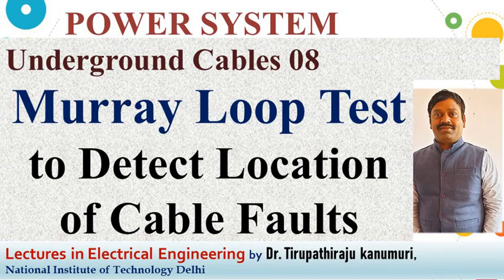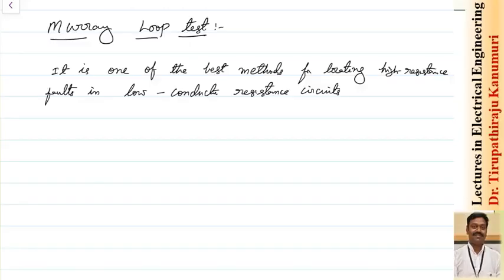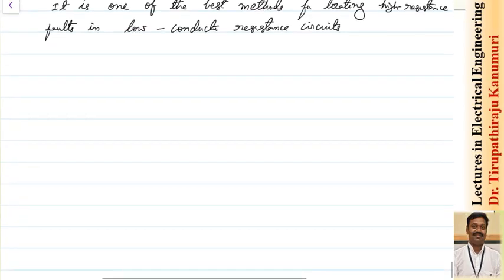Today we are going to see the Murray loop test for finding the short circuit and earth faults of a cable. It is one of the best methods for locating high resistance faults in low conductor resistance circuits. The only limitation of this method is you should have at least one conductor which is a sound conductor — a conductor without fault — having the same length as your faulty cable.